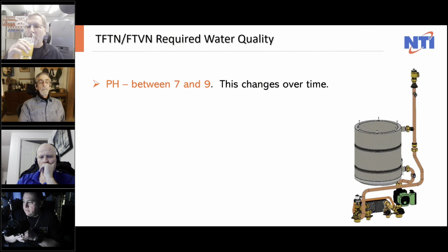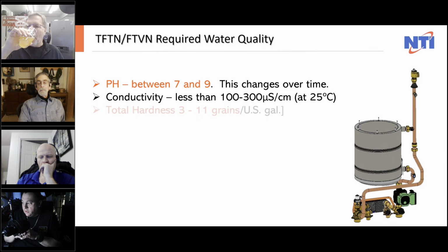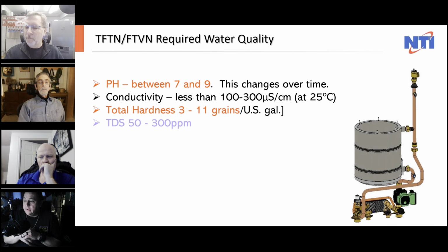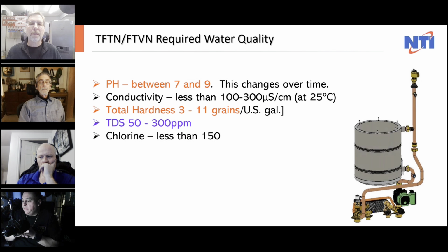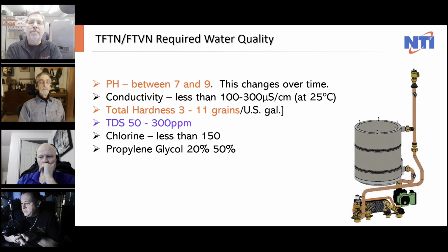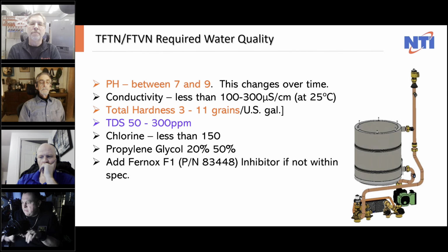Fire tubes have a different pH range, a bit higher. It starts at 6.5 on the water tubes, but once you get up into the fire tubes, you're looking at 7 to 7.5, up to 9 pH levels. And we do have everything published in the manual.